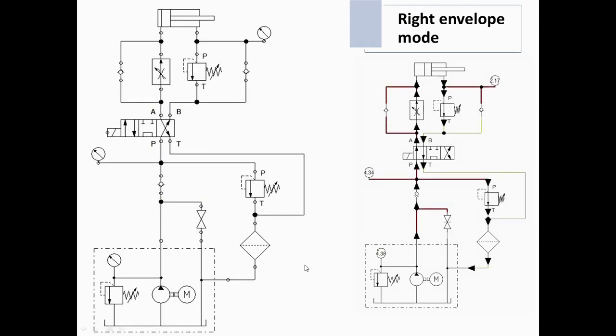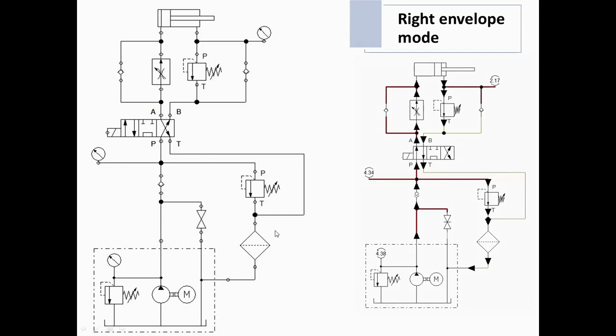In the right envelope mode, the pump pumps the fluid from the reservoir through the open check valve. From port P it enters port B. The other side is not open, so the check valve opens and the fluid flows through to cause retraction of the piston. From the cylinder side, fluid enters in free-flow condition, coming to port A and from A to T, then back through the filter to the reservoir. In this way the working of the double acting cylinder takes place in the hydraulic circuit.